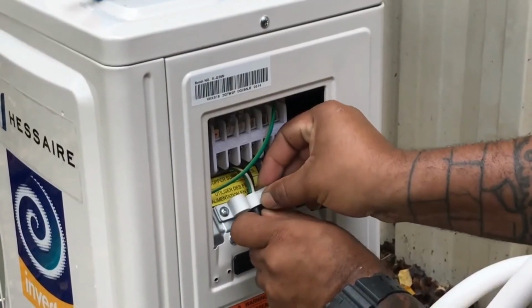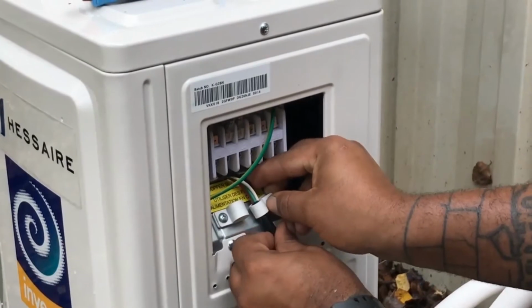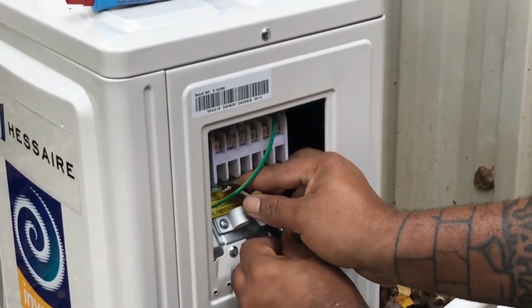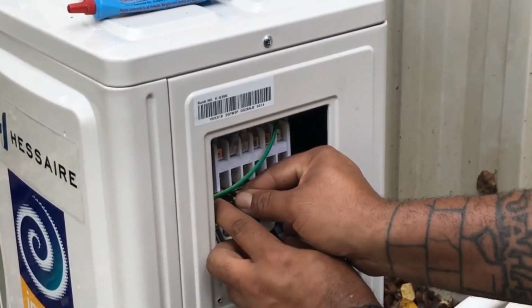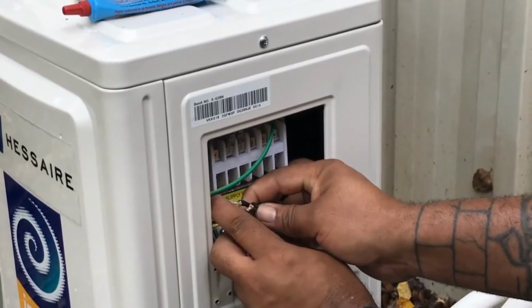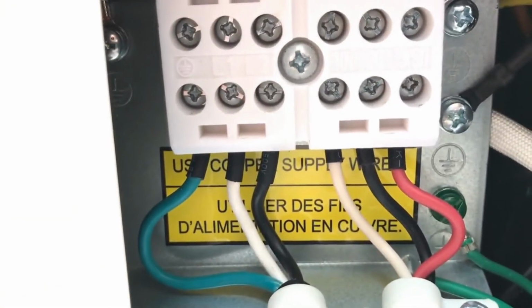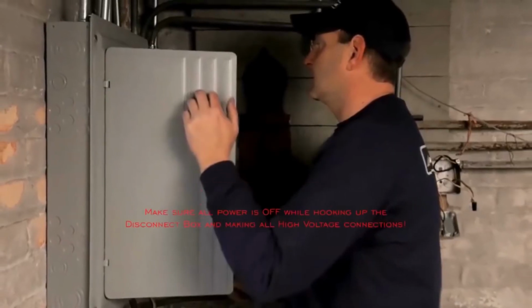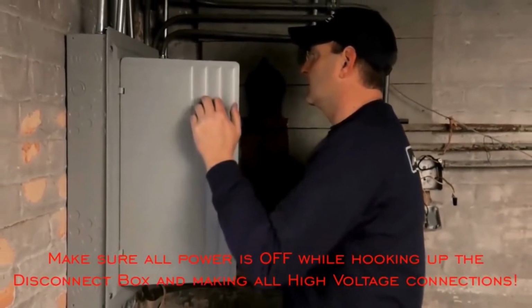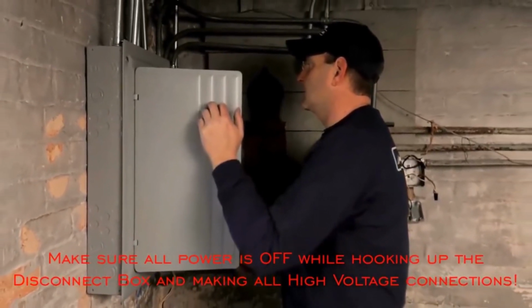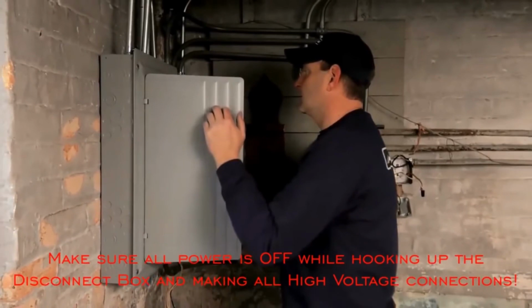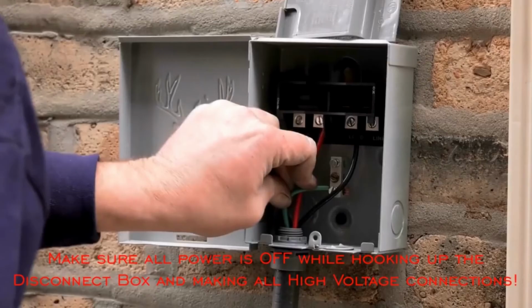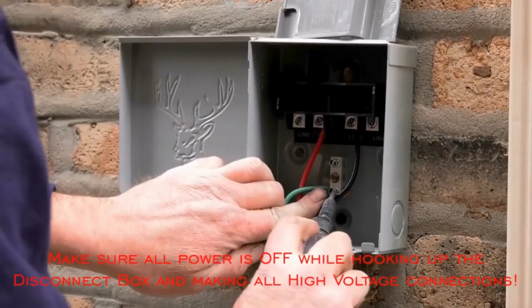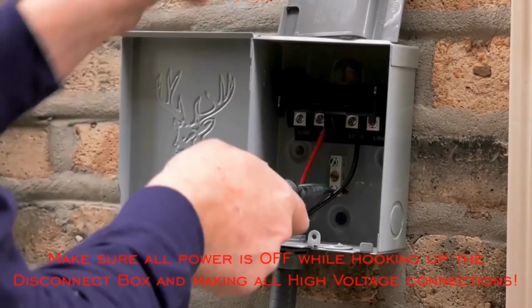Next, connect the multi-conductor wire that is run from the indoor air handler to the associated terminals on the outdoor unit. Double check the color coding to ensure the wires have been connected correctly. The condenser requires 220 volt power from a dedicated circuit on your breaker panel. Run through an exterior mounted manual disconnect box. A qualified technician should install the circuit breaker disconnect box and make a high voltage connection to the condenser.